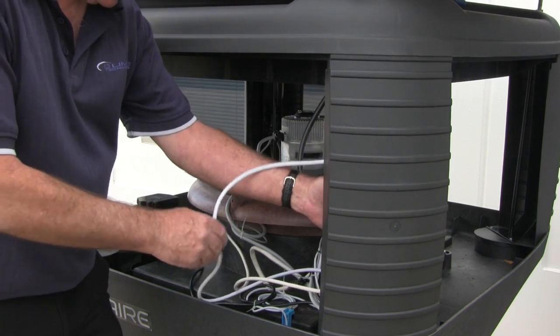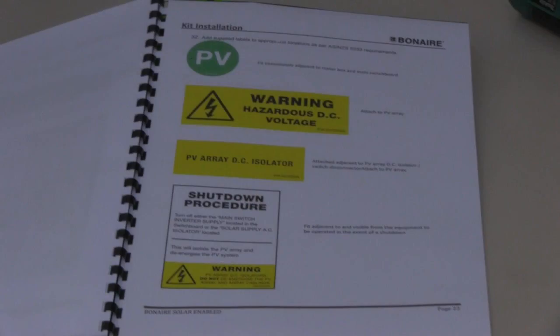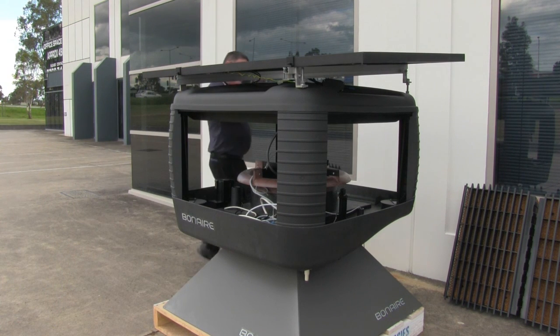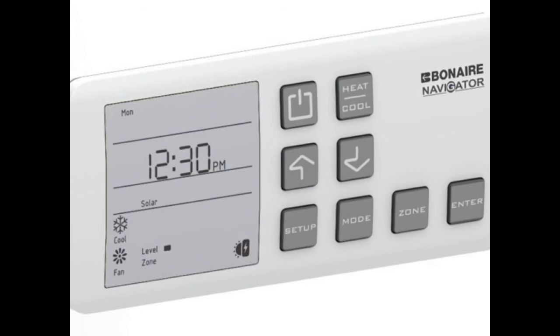Cut off the three-pin plug connection and connect to the inline junction box supplied. Secure to the corner post with P-clips supplied and complete wiring as per Australian standard requirements. Add the supplied labels to appropriate locations as per AS/NZS 5033 requirements. Check all corner posts and connections are secure. Refit the louvers to the chassis and make sure that all Navigator thermostats are solar enabled.